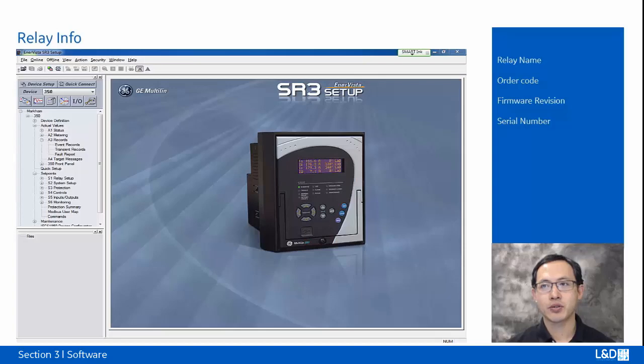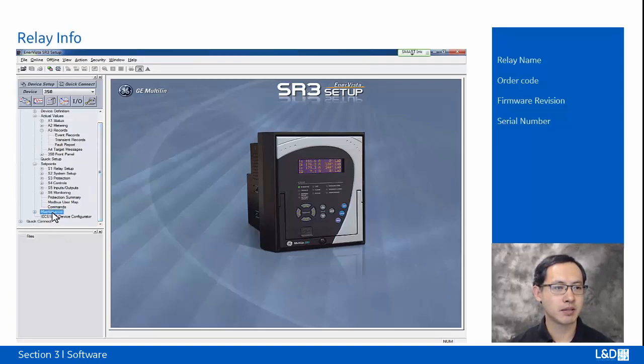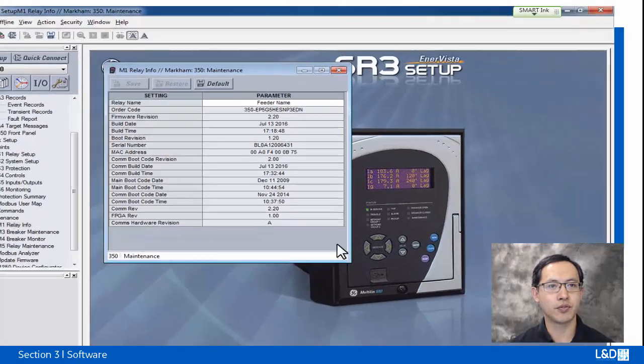The last piece of the actual values is very important. It's the relay order code, firmware numbers, and the serial numbers. And for the 3 series, this is different from other Multilin relays like UR relays or 8 series relays. For these relays, the order code, firmware number, and serial number are under the actual values. But for the 3 series, this information is under the maintenance. So in order to check the relay name, order code, firmware version, and the serial number, we need to open the maintenance and click M1 relay info.